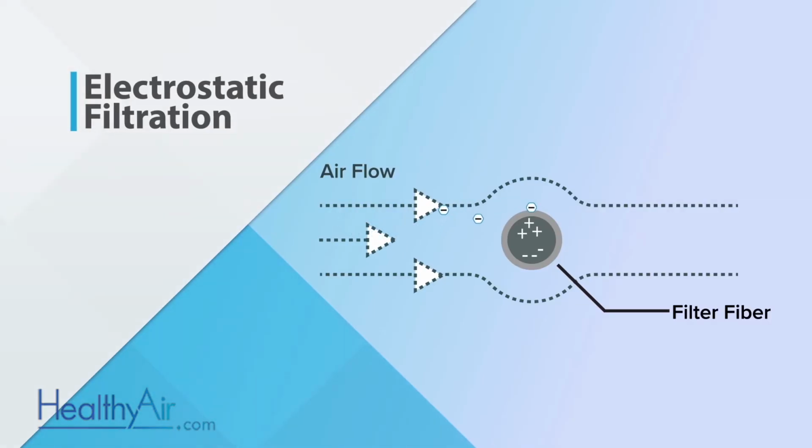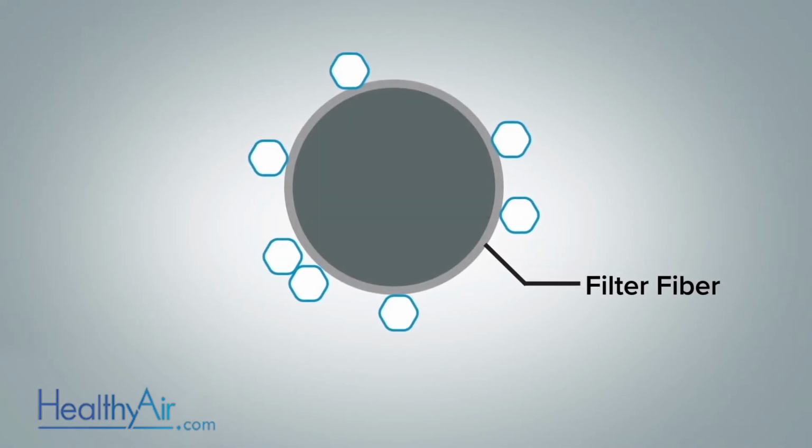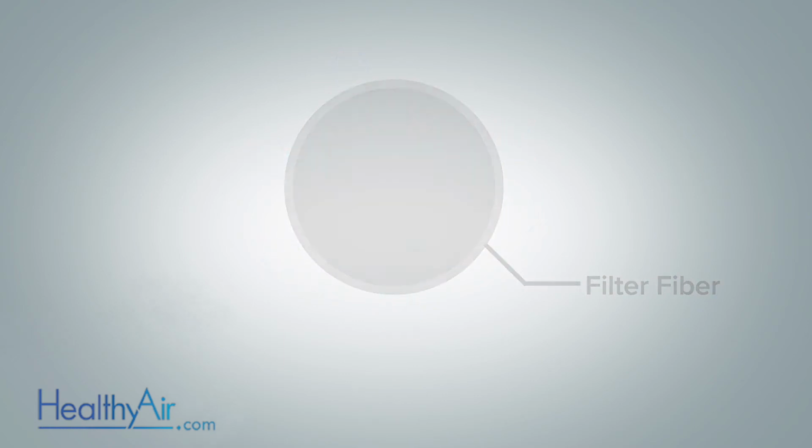Electrostatic filtration means adding both a charge to the particles and microorganisms as well as a polarizing charge of an opposite polarity to the filtration media. One is charged positively and the other negatively. This causes the particles and pathogens to be attracted to the filtration media, producing a high probability of capture on the filter media. There is an additional role that the electrostatic filtration provides, namely the destruction of the microorganism captured on the filter media.